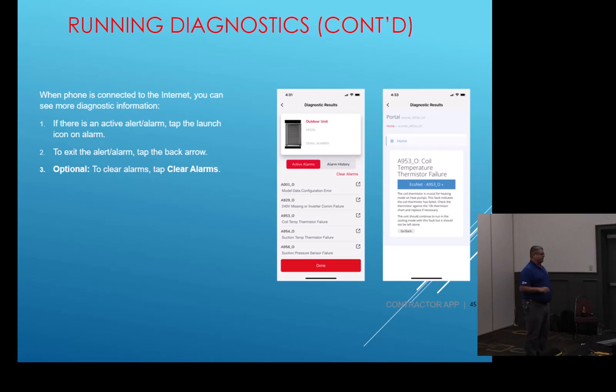So if you get that alarm, basically it's just bad. It could be corroded, okay? We make sure when we put these thermistors on, you need to sand the copper good. And I have guys take electrical tape and wrap it to seal it so no air gets into it, because it's sitting on a cold suction line, right? And if air gets to it, it creates moisture. So if we seal off that air, we don't create that moisture and create that corrosion. So it could be just corroded, but more than likely, it's probably bad. But this is just a real simple one.